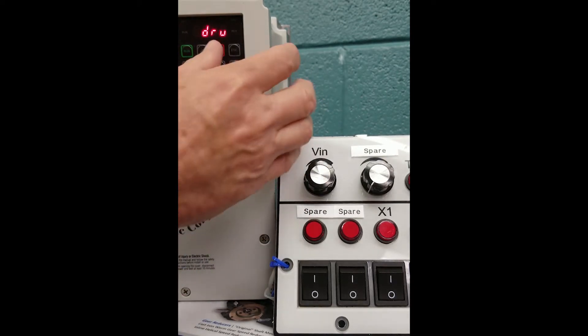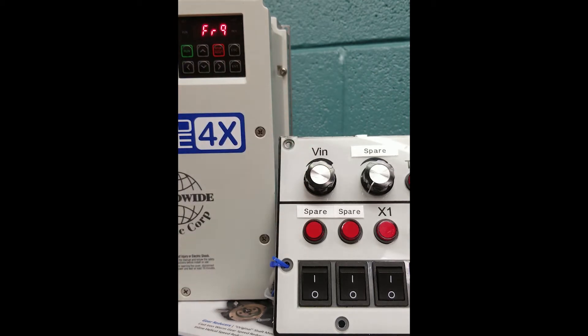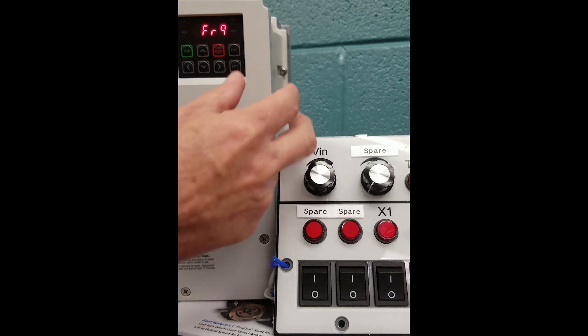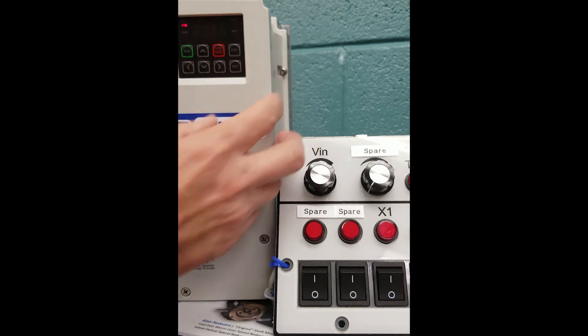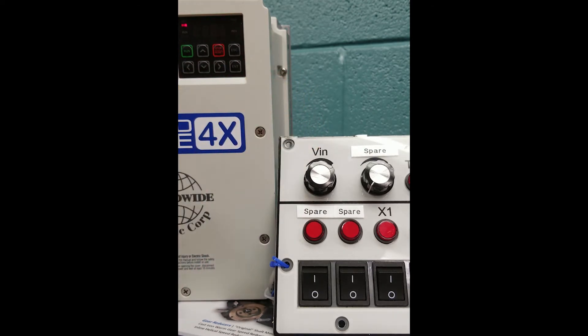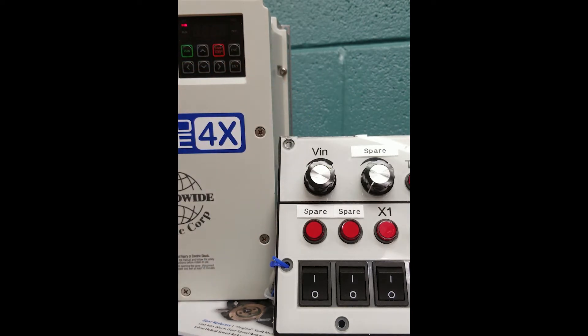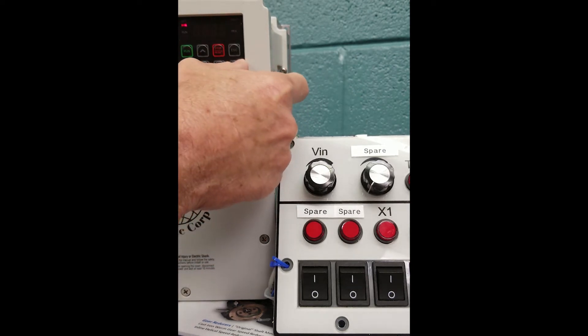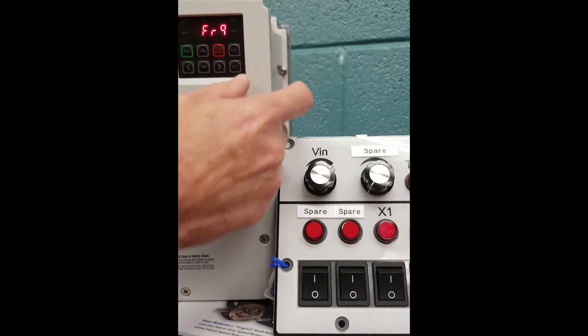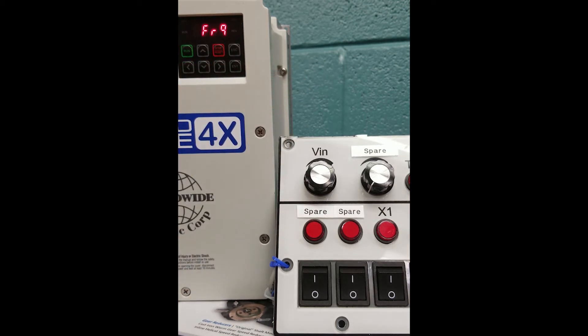Scroll up again, and we're going to see FRQ. In FRQ we're going to hit enter there, and we're looking for our frequency setting. Factory default is 0 for keypad. We need to change that to a 2 to be looking from the terminal strip. Hitting enter twice to store those parameters.